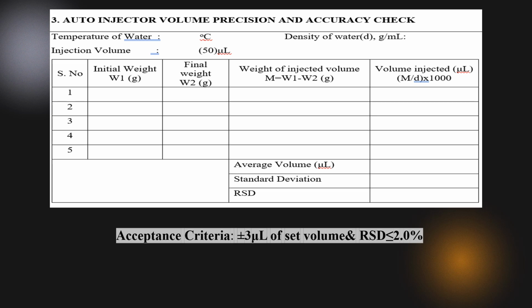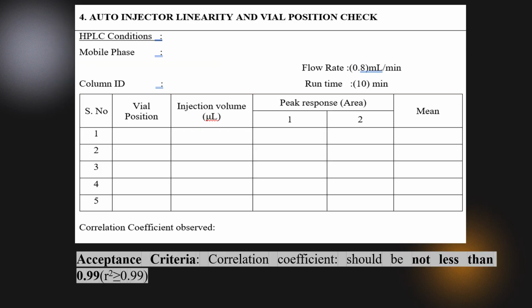And you need to take 5 readings of this. And the RSD of this is calculated. It should be less than or equal to 2%. And acceptance criteria is plus minus 3 µL of the set volume.